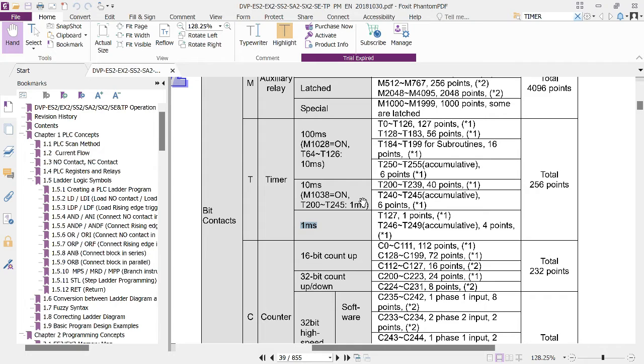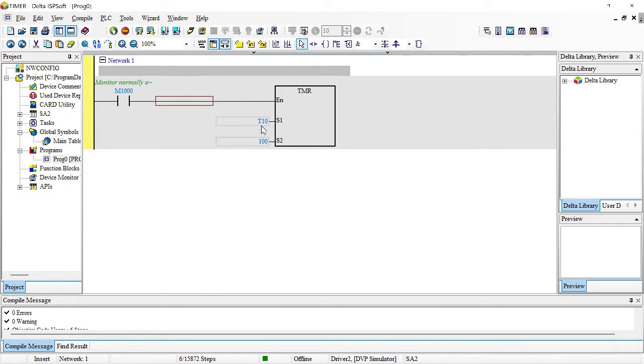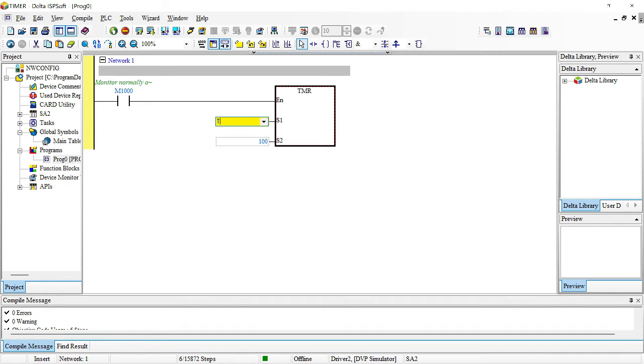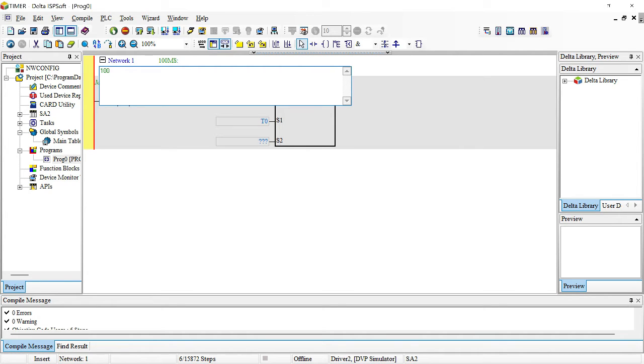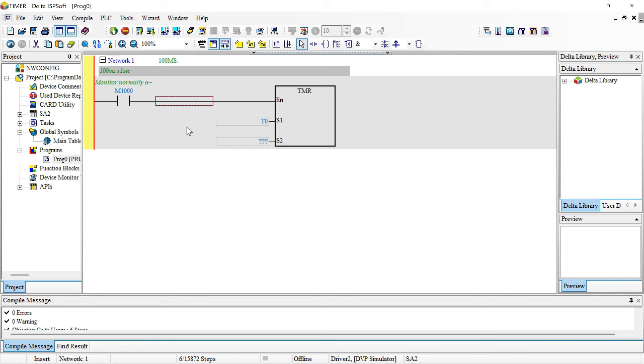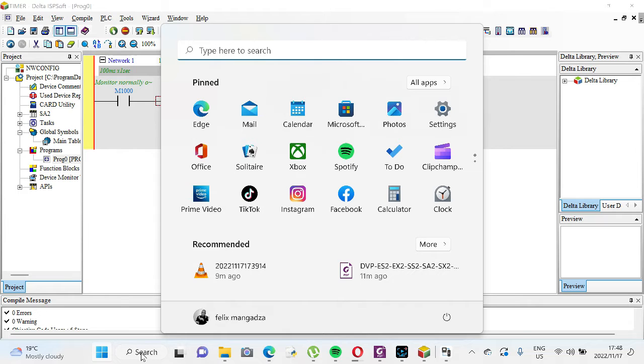We're going to deal with the range of T0 to T127 under the 100 millisecond time base. T10 falls within this range so I'll use T0 and type 100 milliseconds as our time base. Now where does this come in? It's like 100 milliseconds times the seconds that you want. If you say one second, the PLC is saying one second times 100 milliseconds. If you say two seconds, it's two seconds times 100 milliseconds.